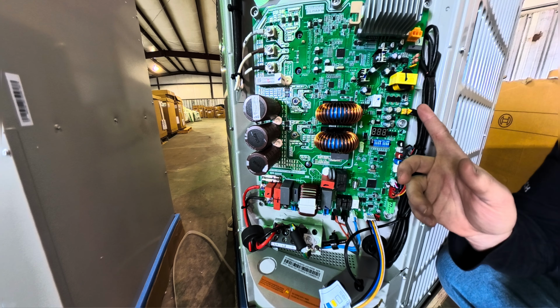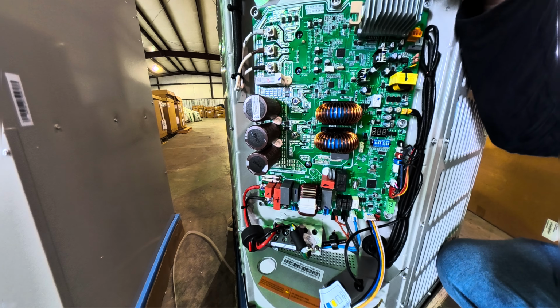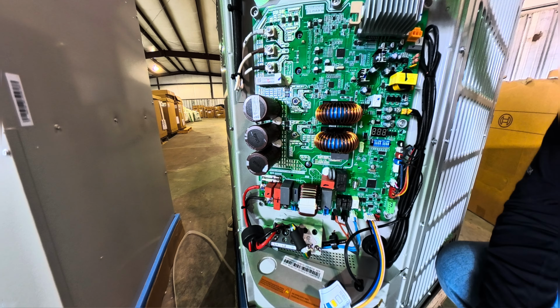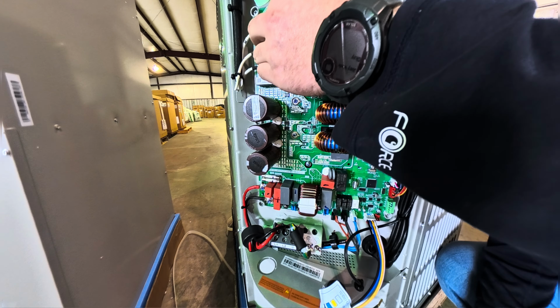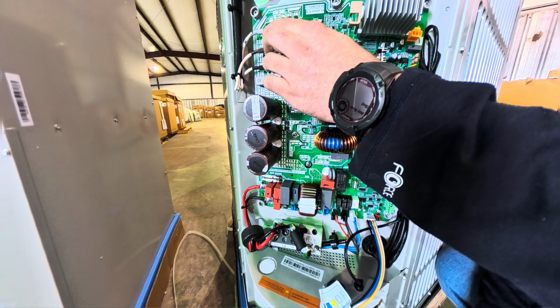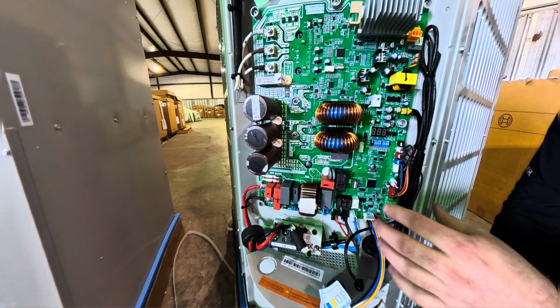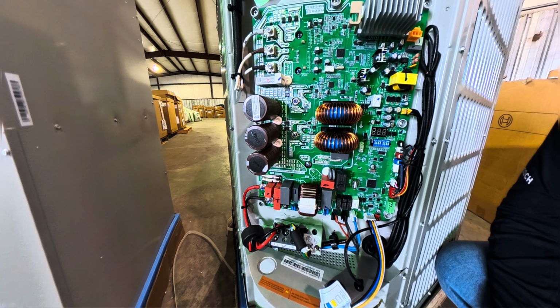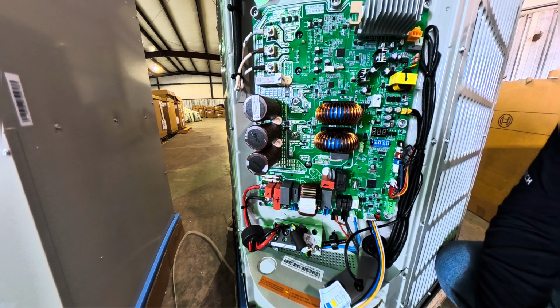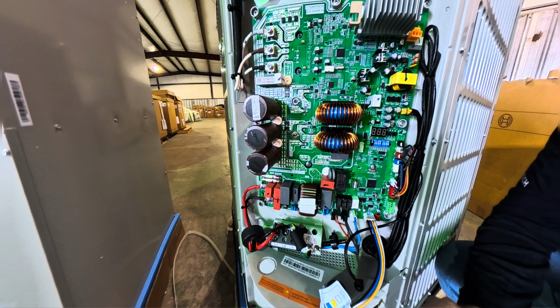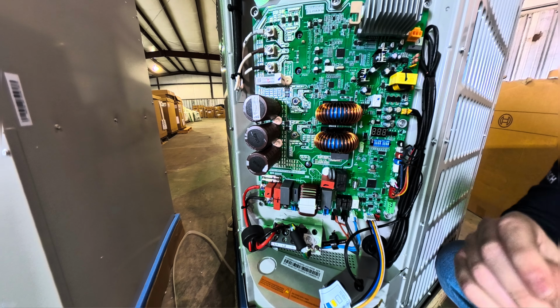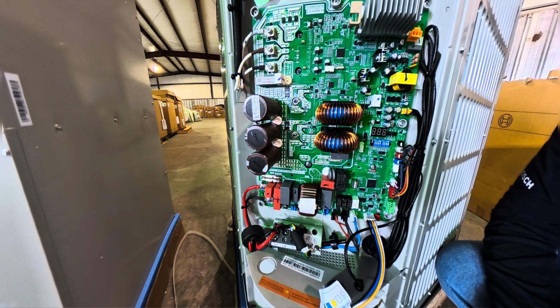Going up, we have a high pressure switch here. We have our 11-speed ECM outdoor fan motor here, and we have our compressor here. Essentially, this is a 3-phase compressor. It's taking AC voltage, turning it into a very high DC voltage, then back to a 3-phase AC voltage to control our compressor so it can ramp up and down. It is a true inverter. Every single hertz is a different speed. It will show you on the control board what hertz it is running, so you know what speed it is running.